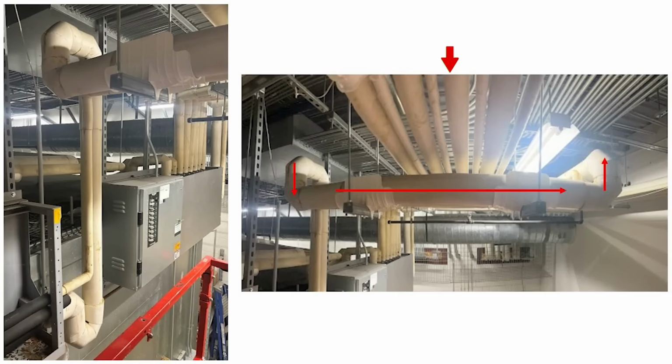And then I set my condenser on the roof line. Well, that pipe is going to go through a gooseneck. It has to penetrate the roof in a weatherproof manner, right? So we typically come out of that gooseneck, and then what we typically do is just U back down to the roof deck and strap our pipe along the roof deck to the condenser, right? Well, guess what? If I'm then going up to my condenser, oh yeah, giant U, right? We've just created a huge U. What is that? Well, U is a trap. And the farther that run is, the more oil that is going to hold in that suction pipe, right?